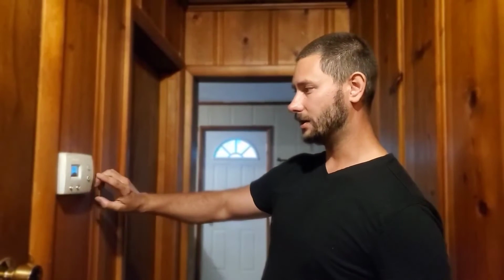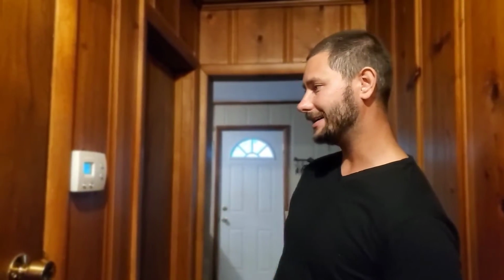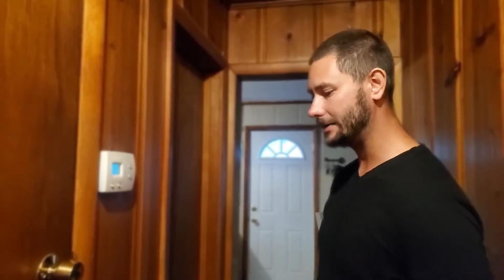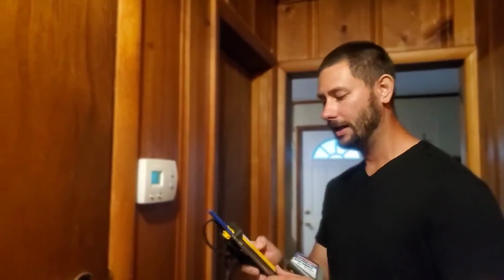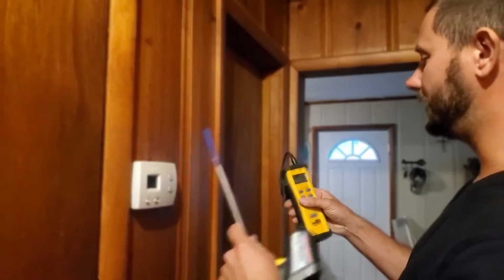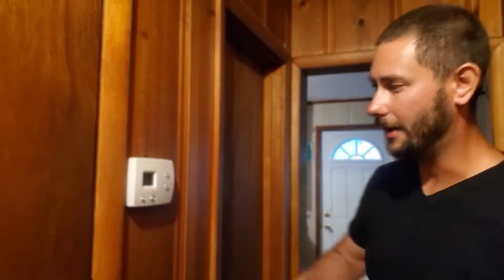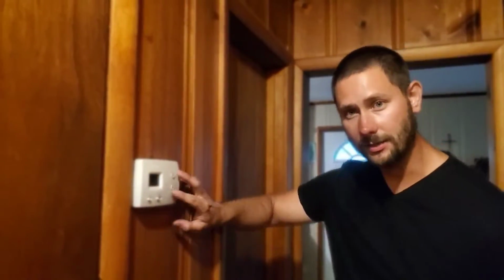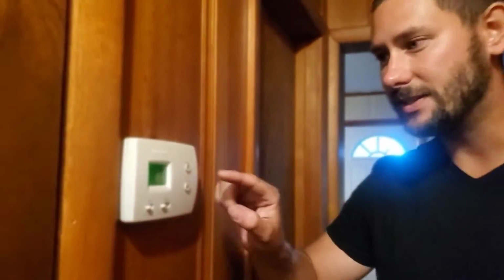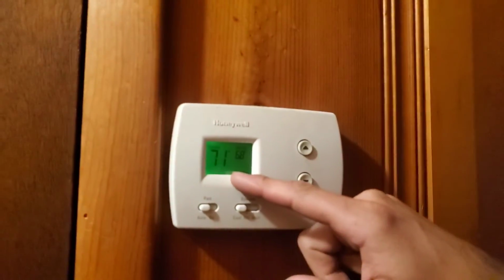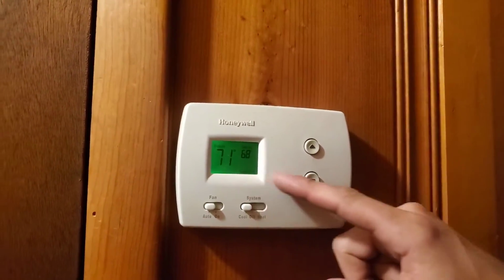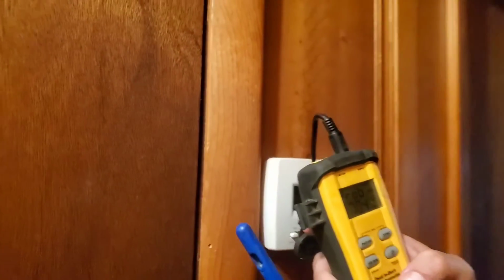So let's just rule out the air conditioner first. How do we do that? We check the supply temperature with the probe. Here's the thermostat - inside temperature is 71, set to 68. Let's go over to the supply vent and stick this probe in, and we're going to measure the temperature. If it's 71 inside, when we measure the supply vent temperature, it should be around 51.